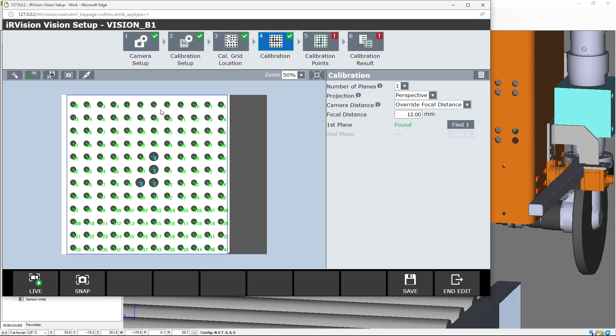We're going to go to the calibration points, and you can see here that these are all the points that we find by the camera, starting from the center and going around. And you're going to see here a table with each one of the points. If you see something in red, that is a bad point, and you can delete that point if you want. So the only thing you need to do is just find out the point number, identify the point number in here, and you just select that point, and you can delete it.